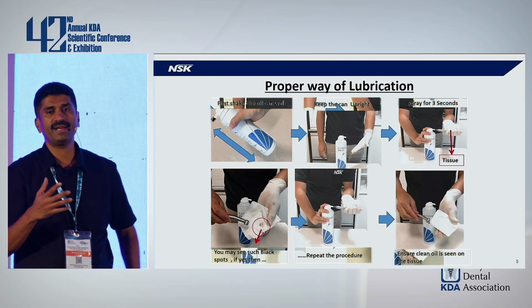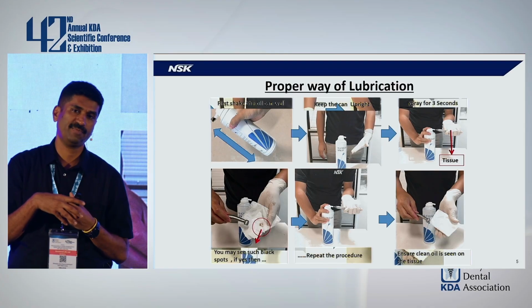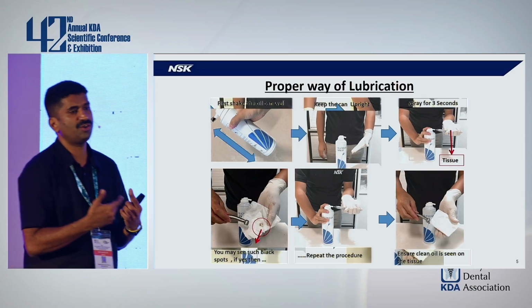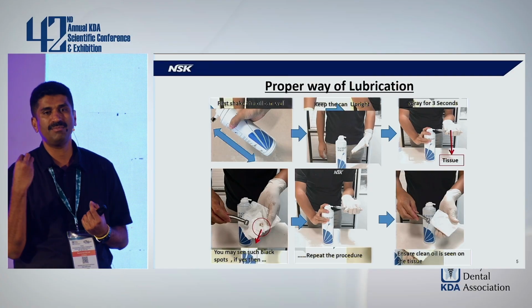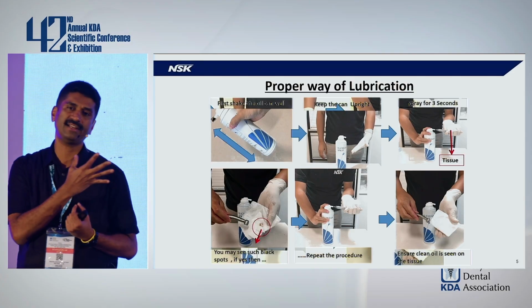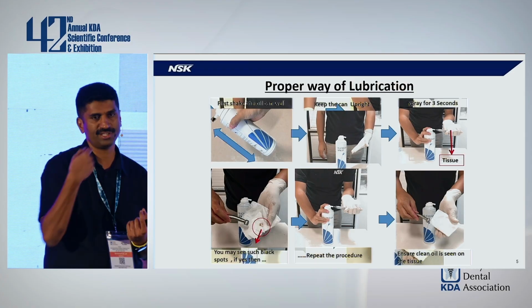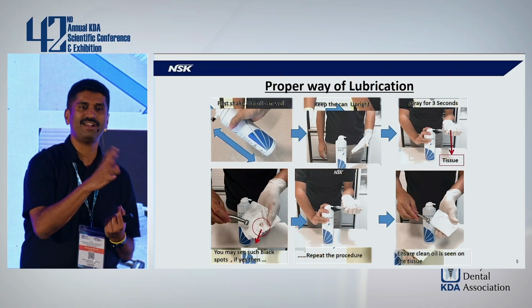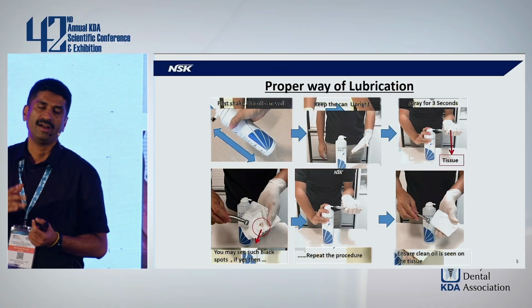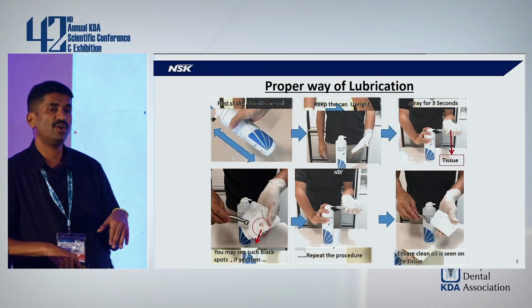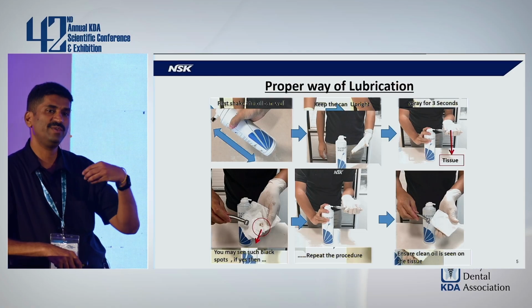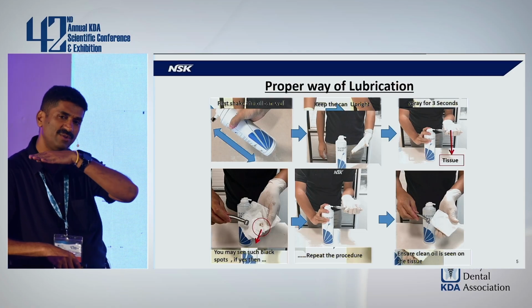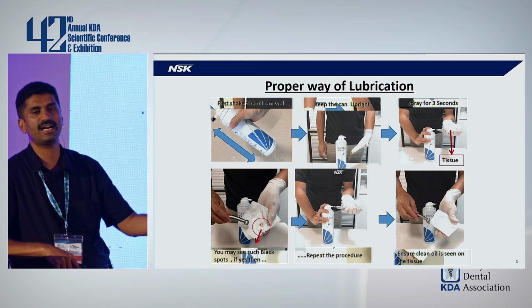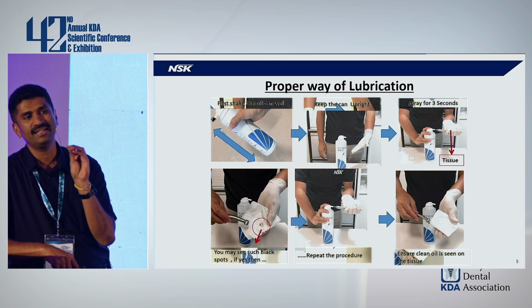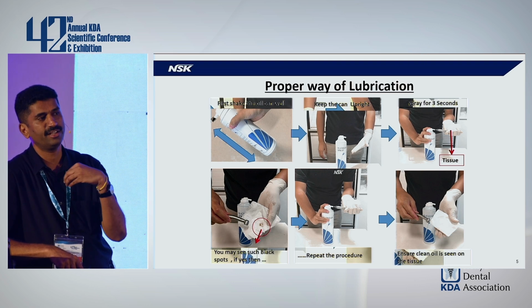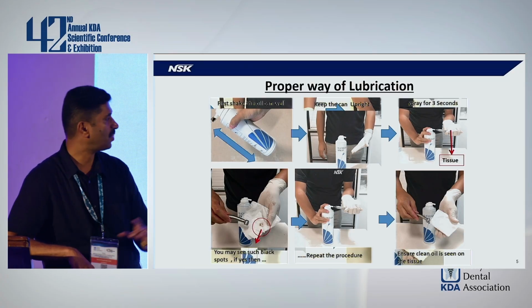sprays, the reputed oil sprays, have a mixture of alcohol in them. So the mixture of alcohol ensures that when you lubricate, whatever blood particles and debris are inside the handpiece, which have come after the operation on your patient, will be flushed and thrown away. On the other hand, the low quality oil sprays will not clean these handpieces. Instead, the oil will just float on such areas and come out without flushing out this debris which has incorporated inside the handpieces. Okay.